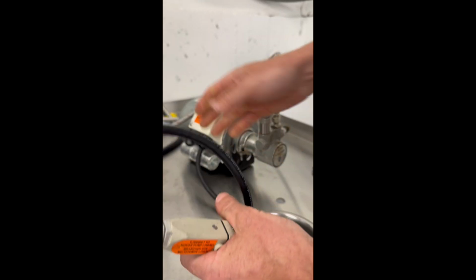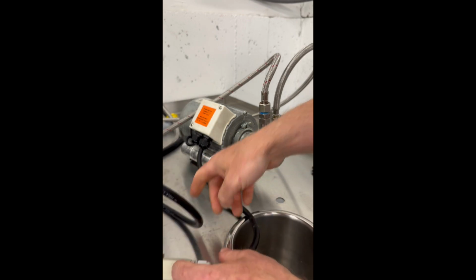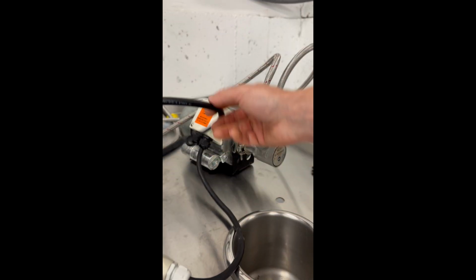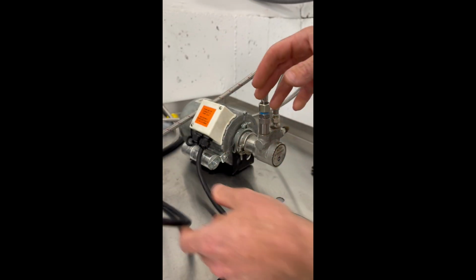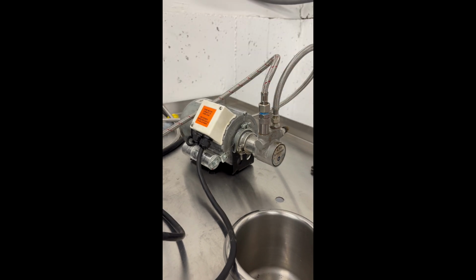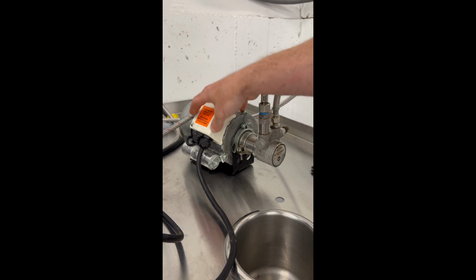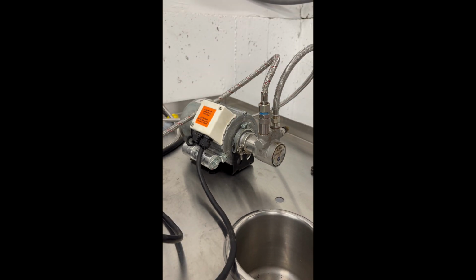It goes for the whole cord, because the next thing that could happen is if this cord gets ran over and shorts out, it will blow a fuse in the machine, and that will cause the pump to also not work. And in that case, there could be other problems as well as the fuse going, but then new cord and a bunch of other things, and possibly a control board. So that's the first thing you want to check.